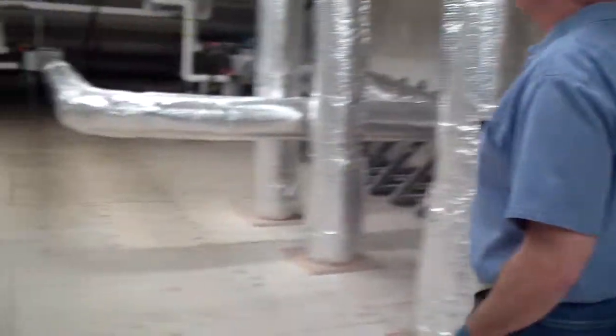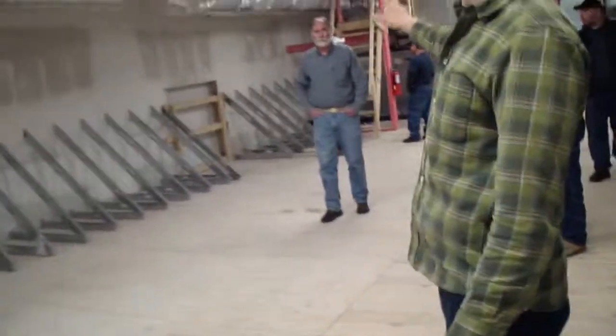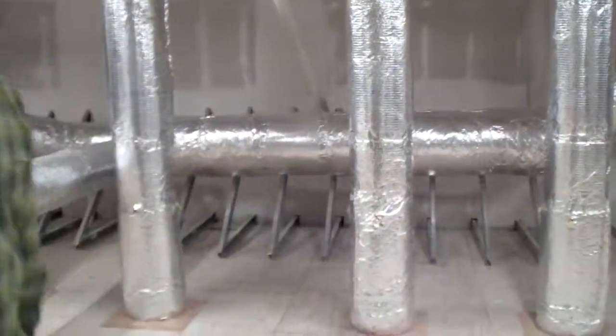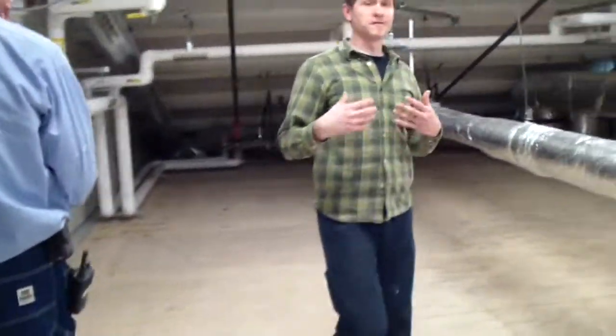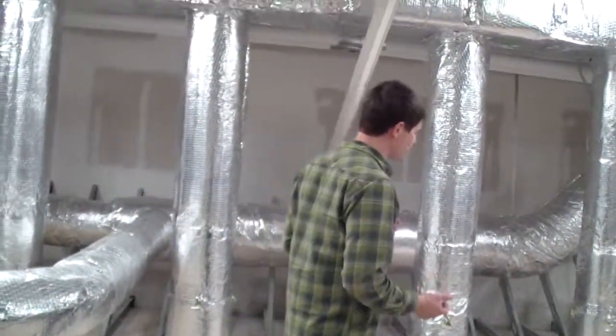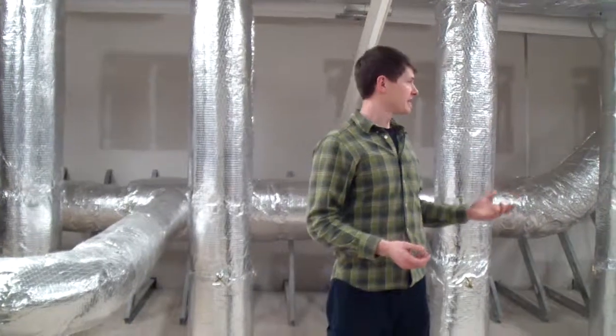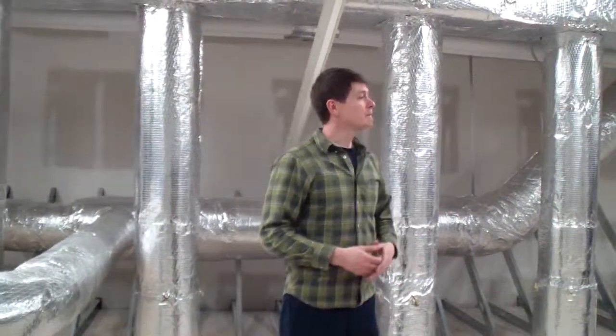So if we want to turn around, we can see 3 of our VAV boxes. They feed the spaces. One of these is for your spinning room. The other 2 are for your mezzanines, I believe A and B. And like I said, the balcony's downstairs. And then another mezzanine was the one that we passed on the way in. Each one of the VAV boxes has its own flow station, so it can actually measure the amount of air going into each room. So it's kind of nice. You can see whether or not you're actually getting flow, whether or not the air handling unit is putting out what it's supposed to.